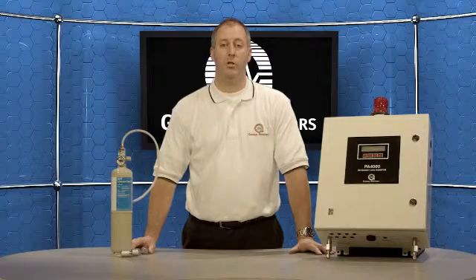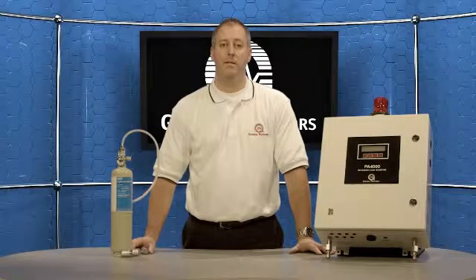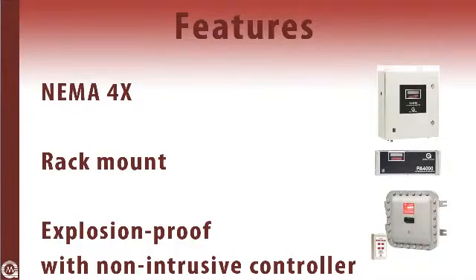The PA4000 is UL and CE approved and is available in NEMA 4X, rack mount, and explosion proof configurations. The explosion proof box comes with a handheld wireless controller which allows access to the menus without the need to open the box and declassify the area.